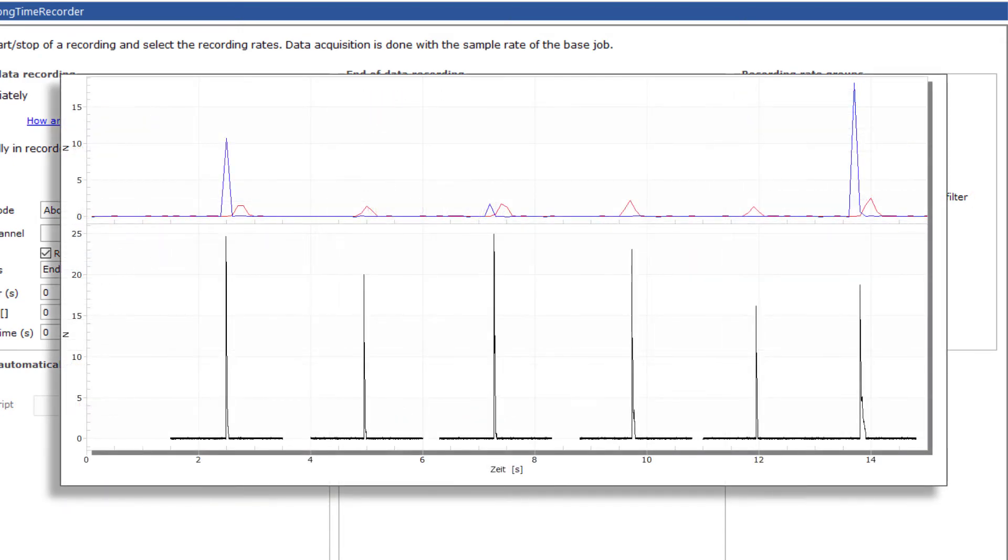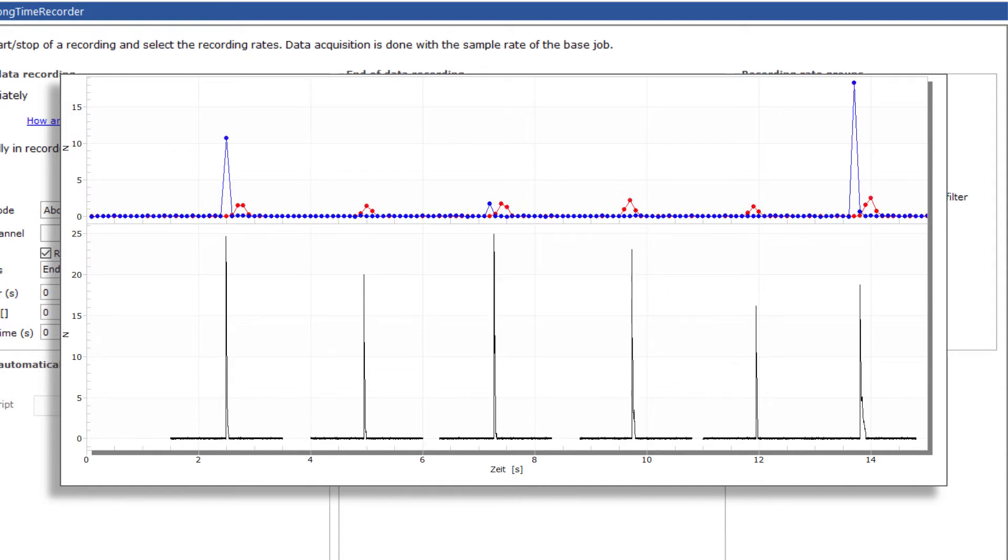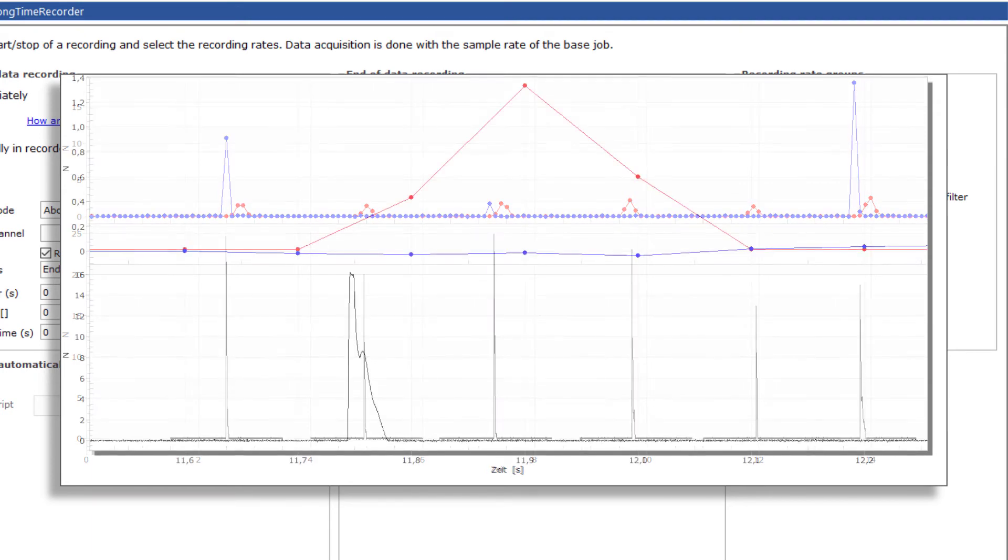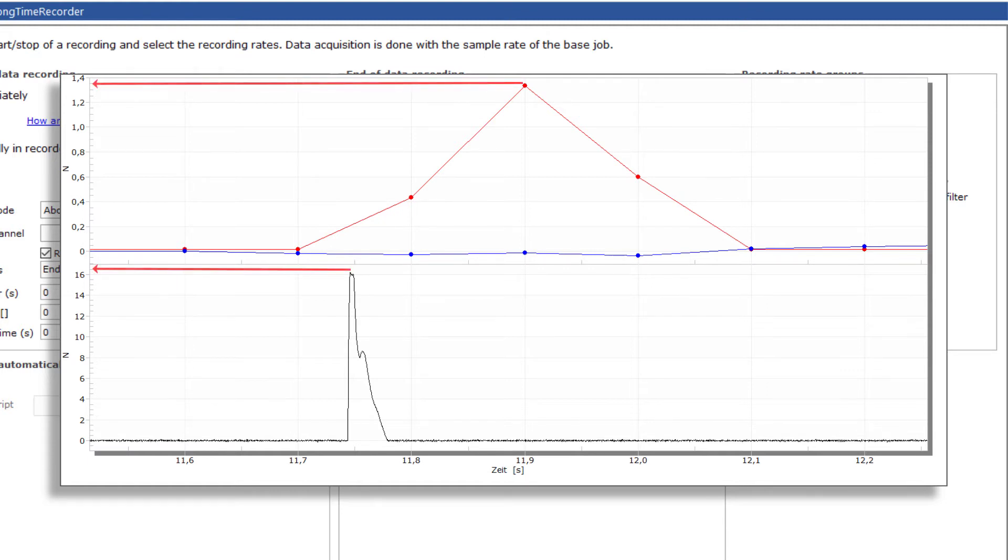This diagram shows a long-term measurement with filter red and without filter blue. As can be seen, depending on the signal curve, short-term pulses are sometimes not visible in the long-term measurement without filtering. The signal deflection could lie exactly between two stored values of the long-term recorder and therefore remain undetected in the data. Even if the amplitudes in the long-term measurement with filter are much smaller than in the original data, it can be seen that there are events.